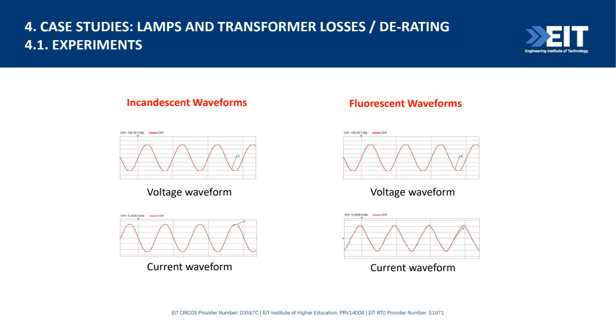What the experimental results show is that if you look at the CFL harmonics, the fifth harmonic is almost 60% of the fundamental current, and the third harmonic is about 83% of the fundamental current. Those are the sharp points you could see. The ninth harmonic is about 41%, and the seventh harmonic is almost 45% of the fundamental. So we do have a lot of harmonics generated by CFLs.